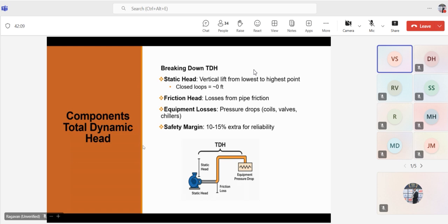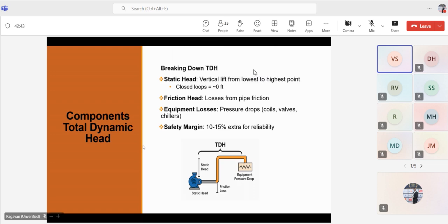Okay, the first important thing is that in a closed loop system, like the one shown in the figure, the chilled water circulates continuously in the closed loop. So water leaves the pump and flows to the chiller and AHU, other components, and returns to the pump, in the same direction. Because in a pressurized system, the static head is actually zero because it's already pressurized. So when the line is pressurized, it's a closed loop system. In a closed loop system, the lifting pressure is balanced by the return of the chilled water flow. So in this scenario, there is no need to consider the static head for the chilled water pump head calculation because the water is already pressurized in the system.